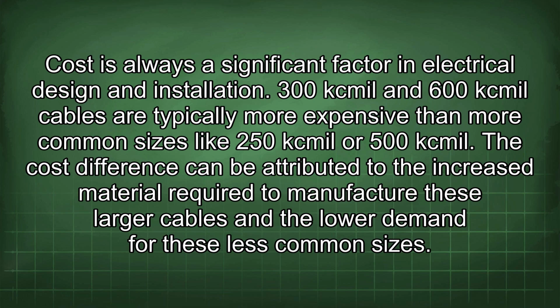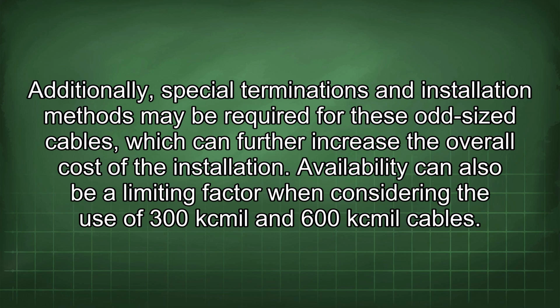Cost is always a significant factor in electrical design and installation. 300kcmil and 600kcmil cables are typically more expensive than more common sizes like 250kcmil or 500kcmil. The cost difference can be attributed to the increased material required to manufacture these larger cables and the lower demand for these less common sizes. Additionally, special terminations and installation methods may be required for these odd-sized cables, which can further increase the overall cost of the installation.